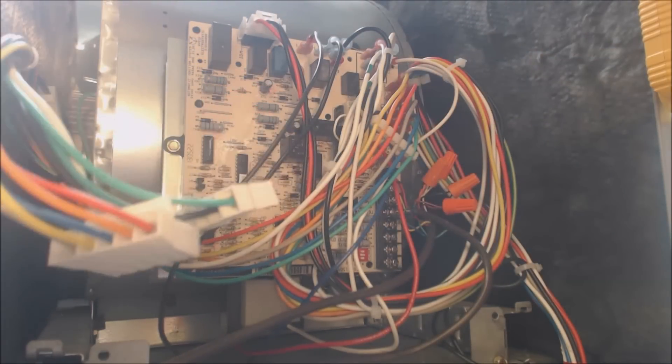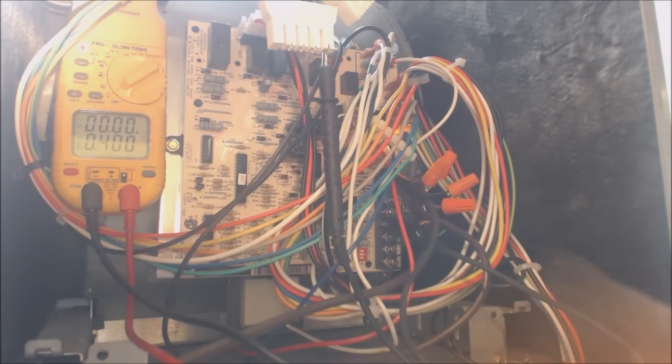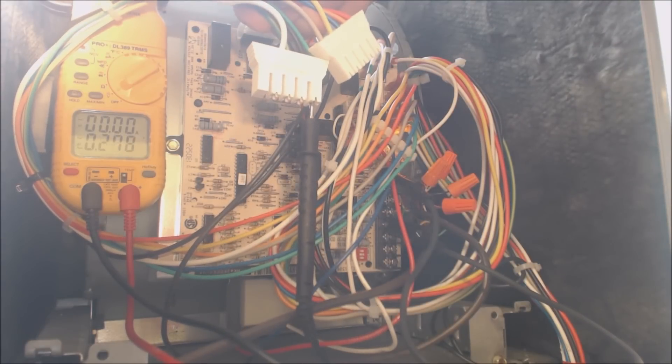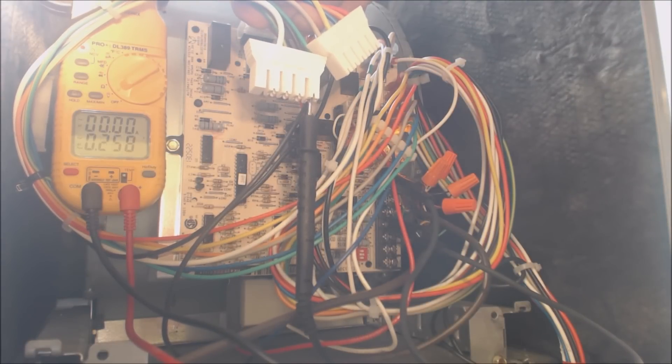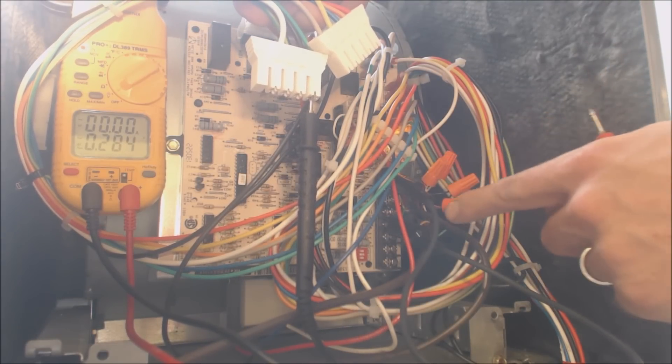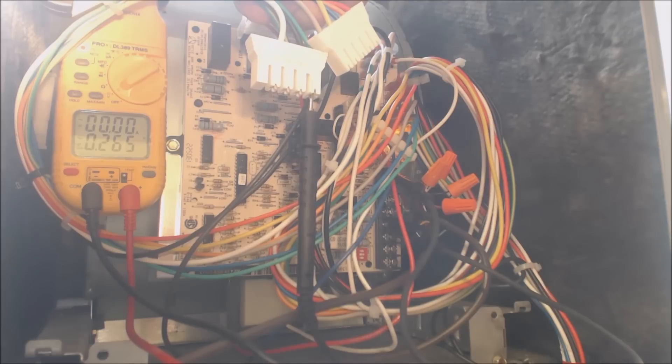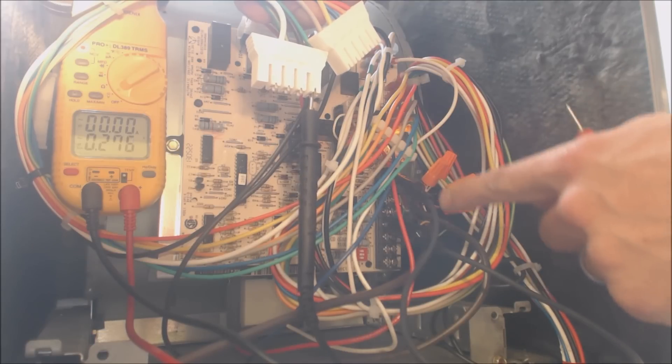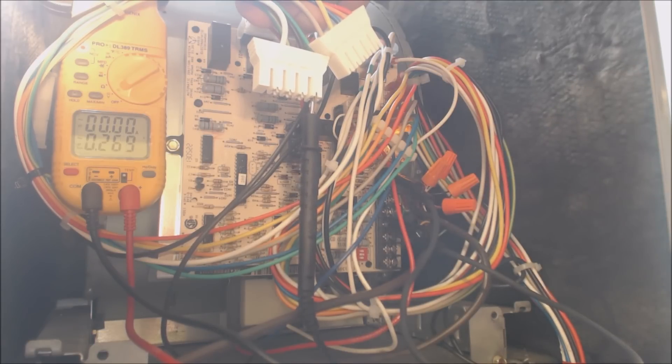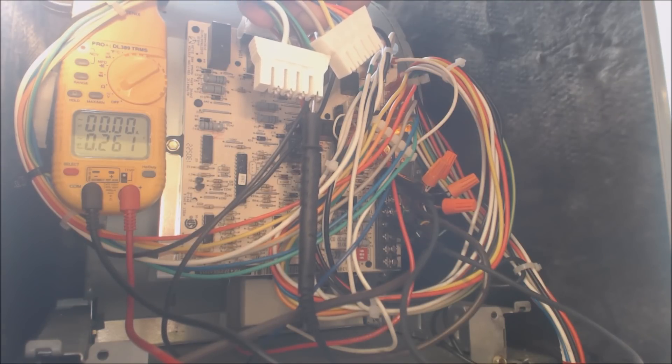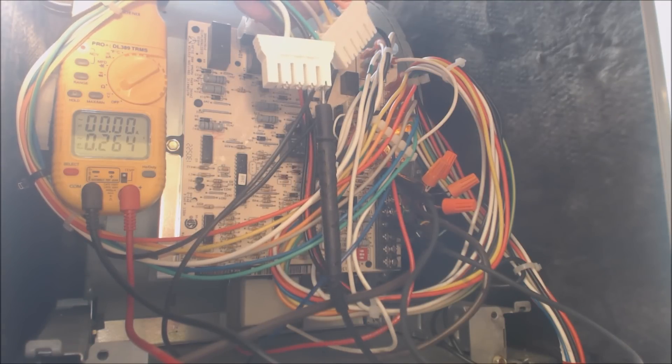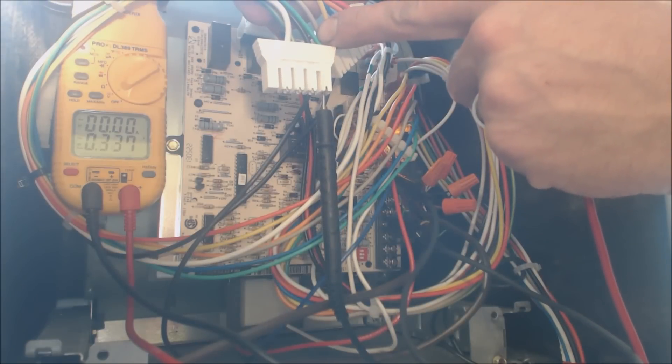So what we're going to do is we're going to set our probes for voltage. So presently, I have the red and green jumper at the control board terminals right there. So we're taking the thermostat wire and thermostat out of play.